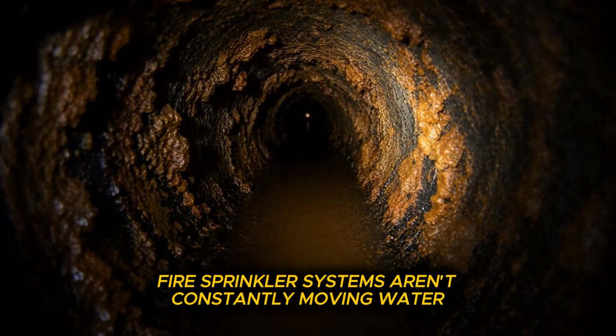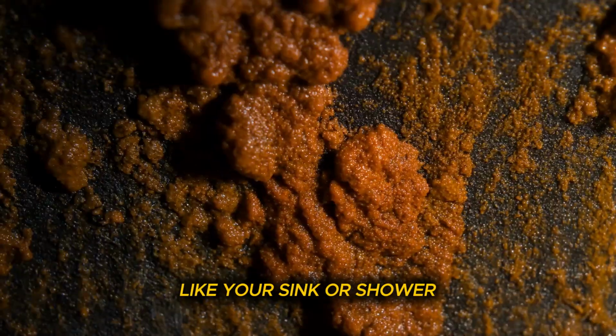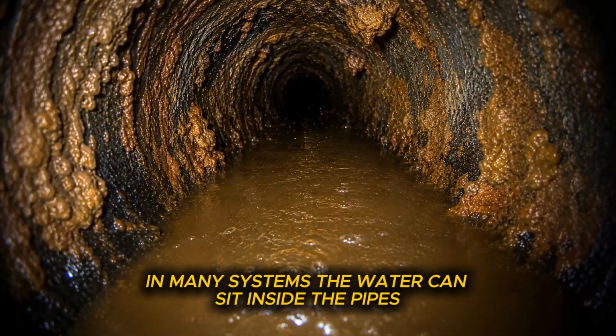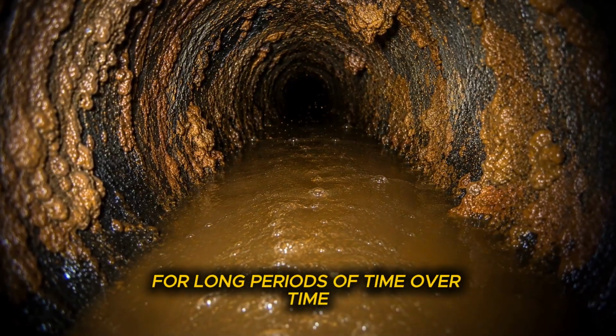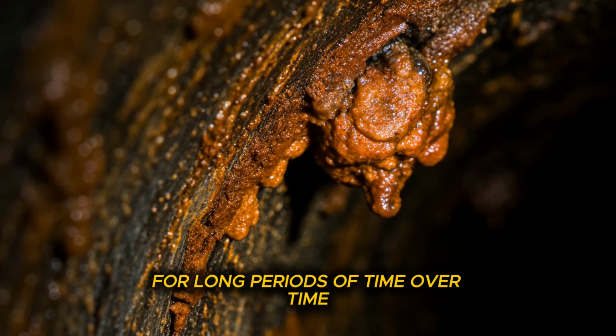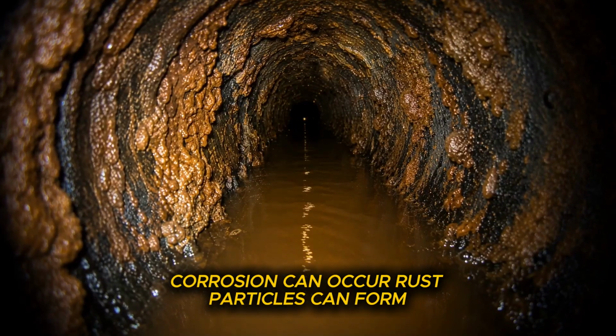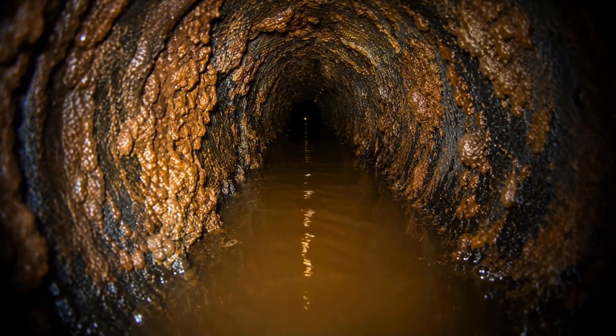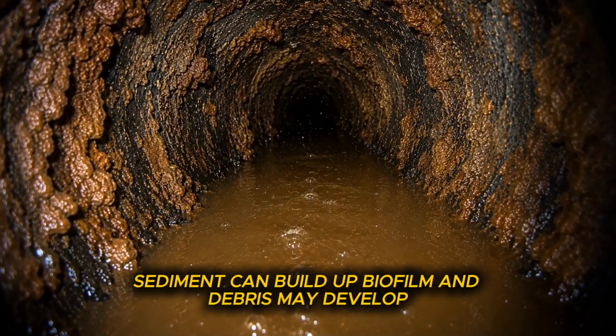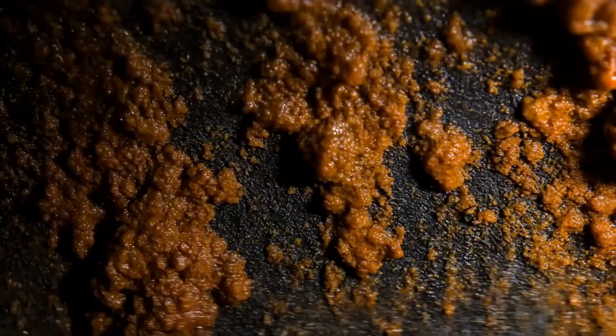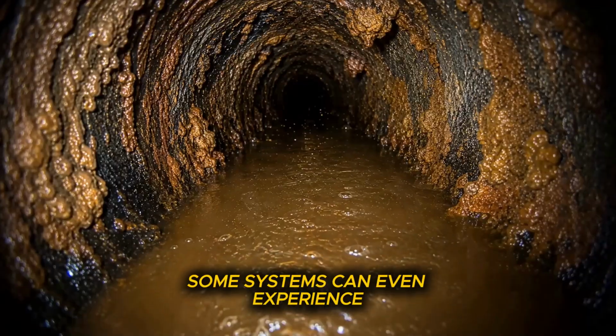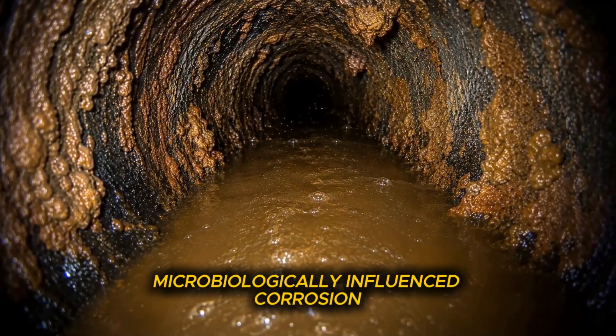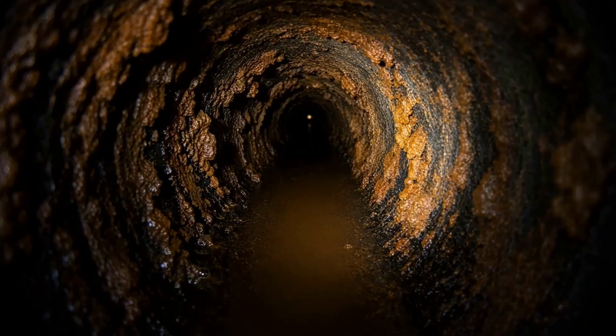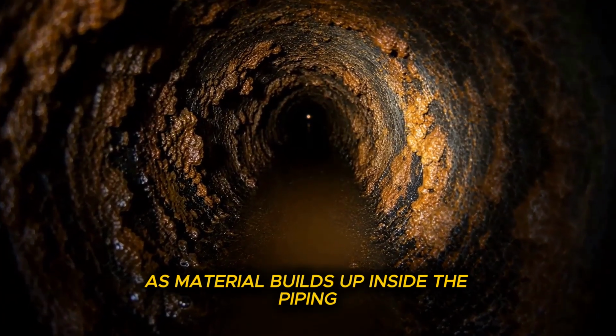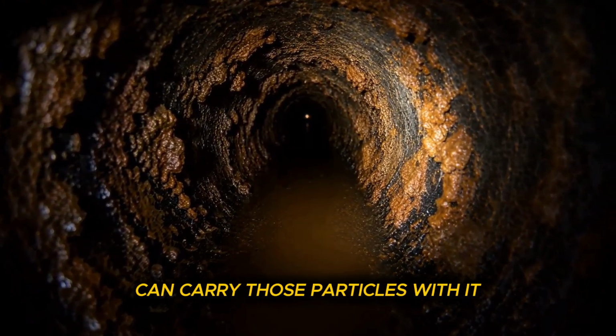Fire sprinkler systems aren't constantly moving water like your sink or shower. In many systems, the water can sit inside the pipes for long periods of time. Over time, corrosion can occur. Rust particles can form. Sediment can build up. Biofilm and debris may develop. Some systems can even experience microbiologically influenced corrosion, also called MIC. As material builds up inside the piping, the first water discharge can carry those particles with it.